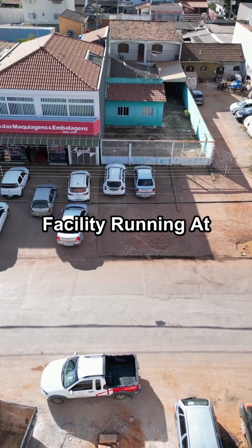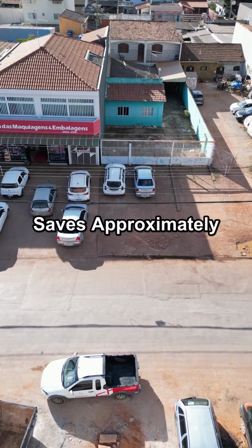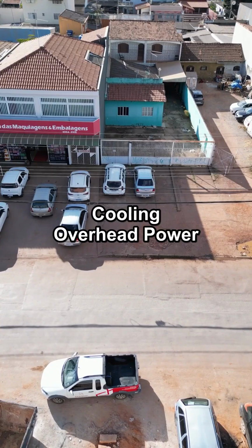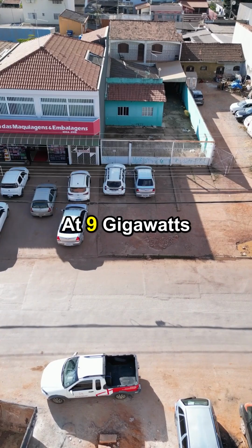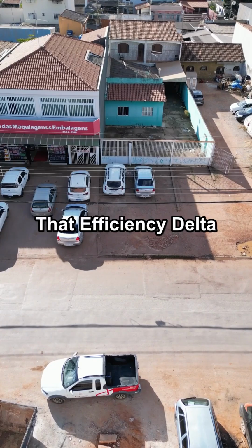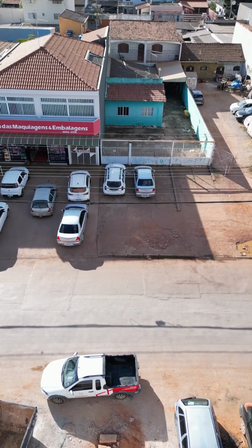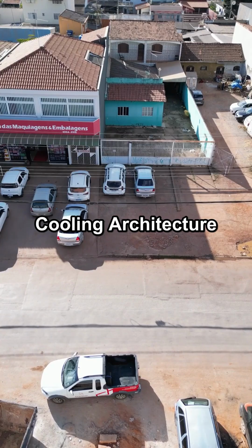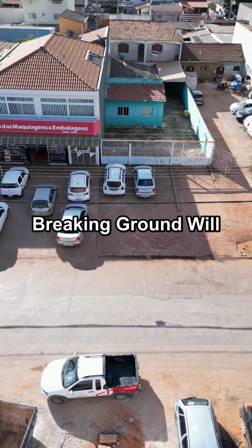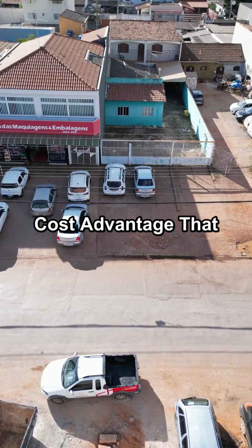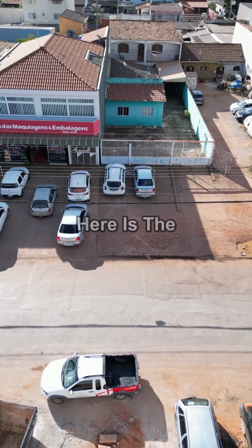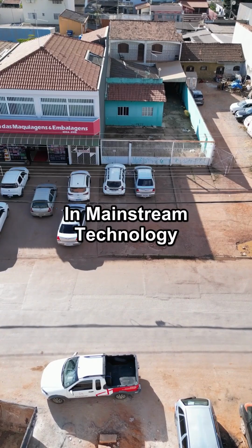A facility running at PUE 1.05 versus 1.40 saves approximately 35% on cooling overhead power. At 9 gigawatts of IT load, that efficiency delta compounds into billions of dollars over a 15-year asset life. The developers who solve cooling architecture correctly before breaking ground will build a structural cost advantage that competitors cannot replicate by just swapping hardware.